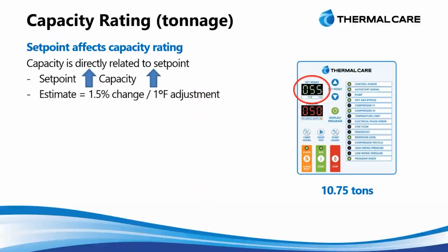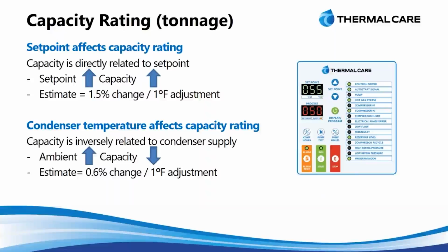The other aspect of a nominal rating was that ambient temperature, or the cooling tower, cooling water condenser. And those are actually inversely related. As that ambient temperature goes up, so as it gets hotter in the air surrounding the chiller, it's more difficult for that chiller to reject the energy out. And so it has to work harder and the capacity goes down. One of the things that I like to point out here is that it's both the water and the air, as they go up or down, they affect that capacity. But when you really get into thinking about this, it's the location of where you're going to put the chiller. And we'll talk a little bit more about that shortly.